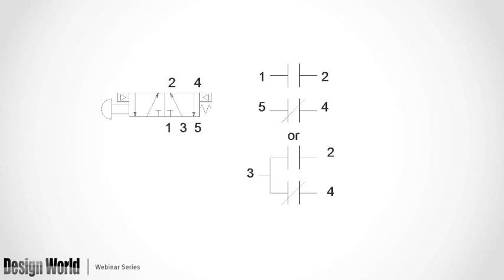And they'll test these things for 1 million cycles overnight. And if they're still running at 1 million cycles, then they're shipped as a new valve. And you say, wait a minute, 1 million cycles on an electromechanical relay is more than the life of many of them. That's just warm-up time. That's just break-in time for an air logic valve. These air valves will go millions of cycles as long as you have clean air to them. That's one of the huge advantages.